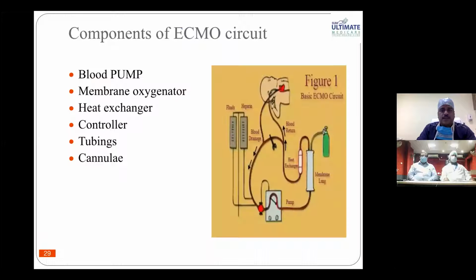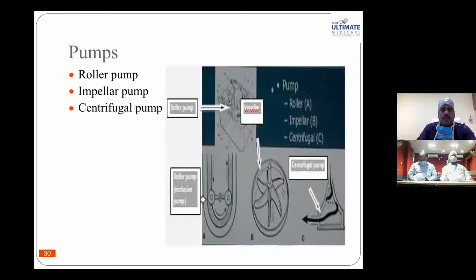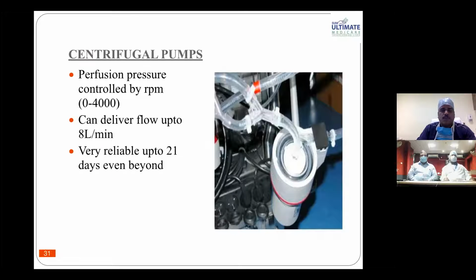Coming to the ECMO circuit and components, definitely it involves a lot of things: blood pump, membrane oxygenator, heat exchanger, controller, tubing, cannulae. In the ECMO circuit, the common pump is the centrifugal pump. Whatever you are using now is a centrifugal pump. The roller pump, which we use in the heart-lung machine, is not used here. The centrifugal pump has a longer durability without much damage to the blood cells, whereas the roller pump has a more damaging effect if you use it on a patient for more than 5 to 8 hours. The centrifugal pump can deliver flow up to 8 liters. It is very reliable up to 21 days. Even people are using centrifugal pump ECMO for more than 50, 70 days.